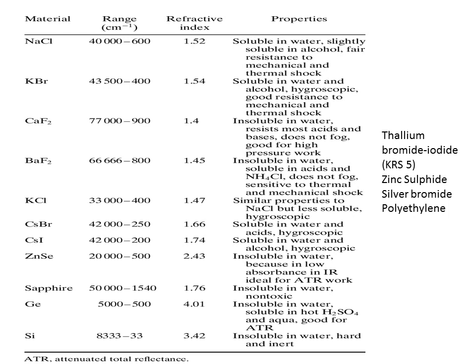Now here you can study even the properties of the material. If you are using sodium chloride or potassium bromide as a salt, these are soluble in water, and so naturally you cannot use them for aqueous systems. Additionally, the solvents should be dried before using. Even a trace amount of water will readily dissolve those salts and the path length of the cell is going to vary.